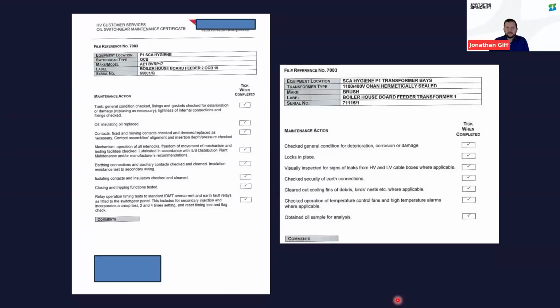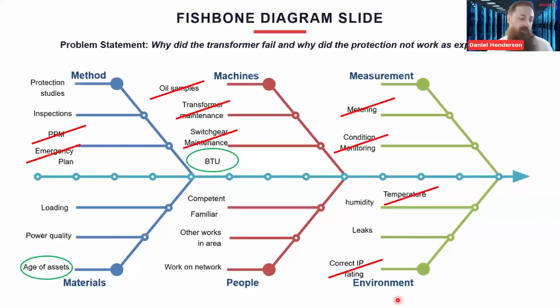Does that form part of this? I don't have the certificate for the battery tripping unit, but I saw it done like the year before. What did maintenance look like on that? So that was checking the batteries, so the voltage on the batteries. It was an old set of batteries, so you had a supply, a fused spur. There was no supply indication. It was just an isolator on the batteries. They tested the voltage, cleaned them down, things like that, and tested the float voltage. And then on the maintenance, tested the output current to make sure there was enough current to operate the electromechanical relays, which I think was around 2 amps or something.